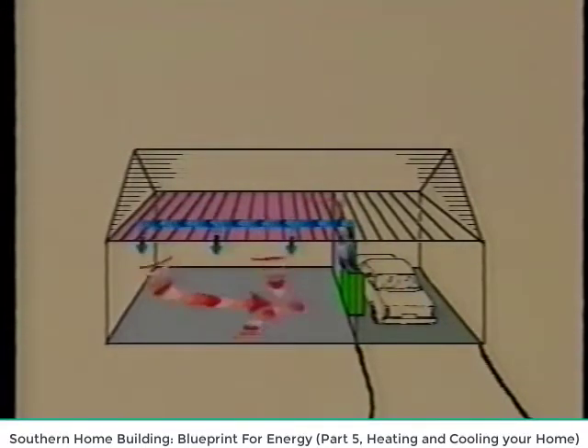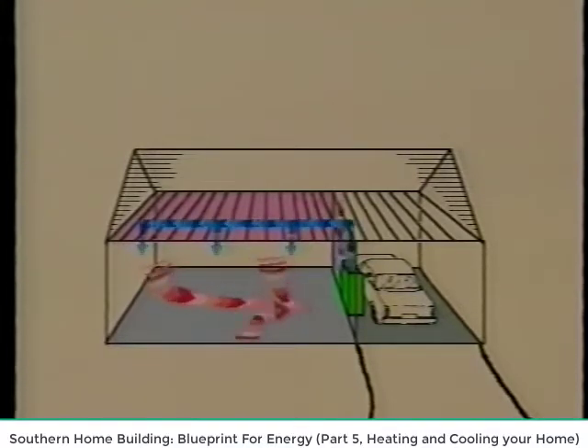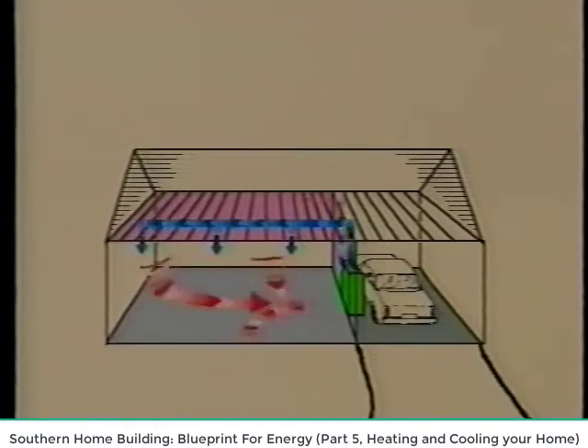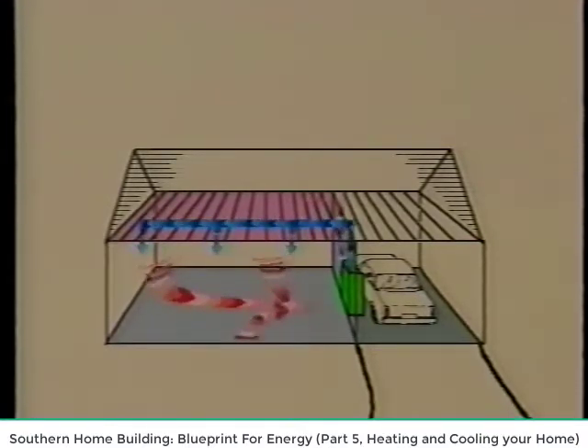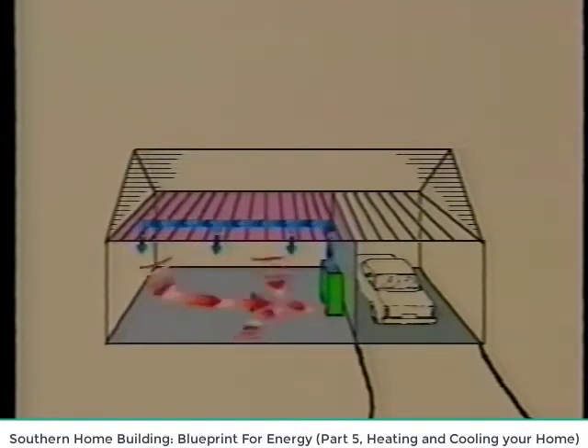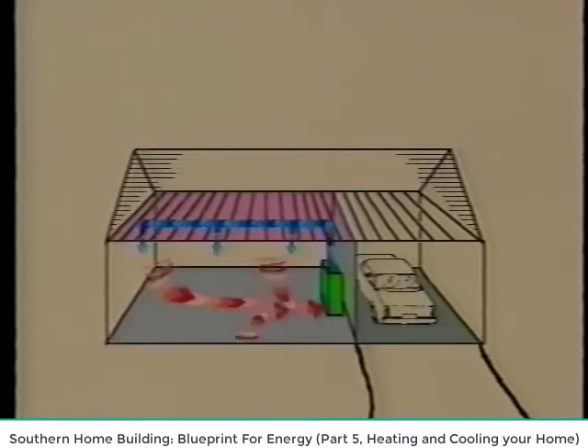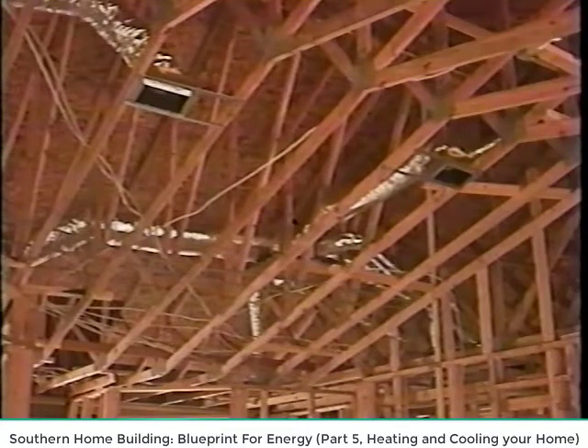A more efficient system uses free air return. A free air return system eliminates the need for the return duct in the attic. The rooms and hallways of the house actually serve as the return duct. To save more energy, the air handler should also be placed inside the house because air handlers leak expensive conditioned air. With less duct work, there is naturally a reduction in duct cost.